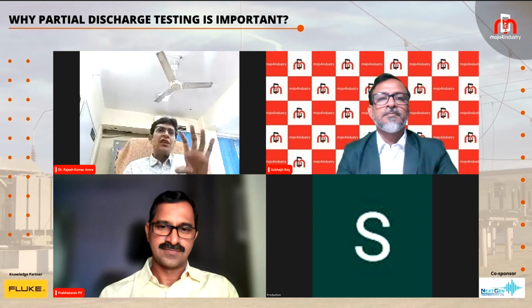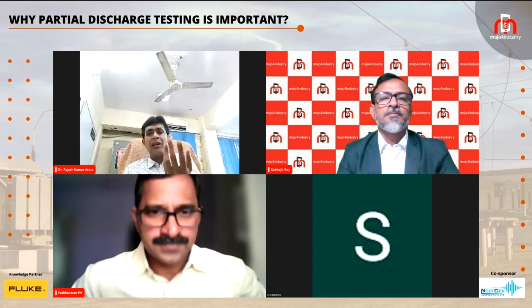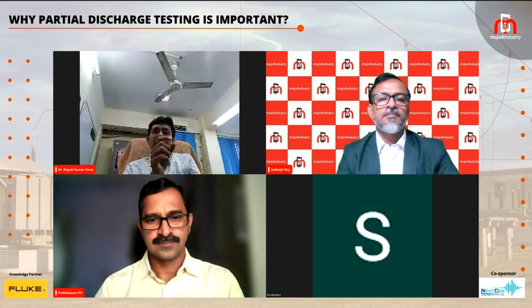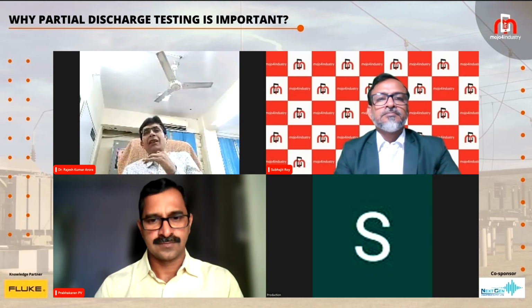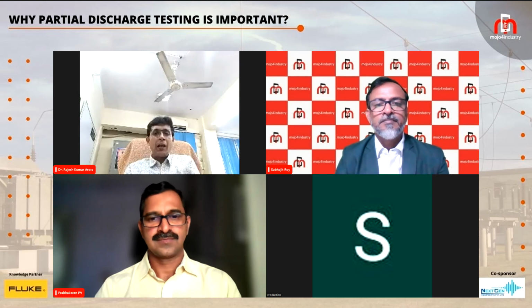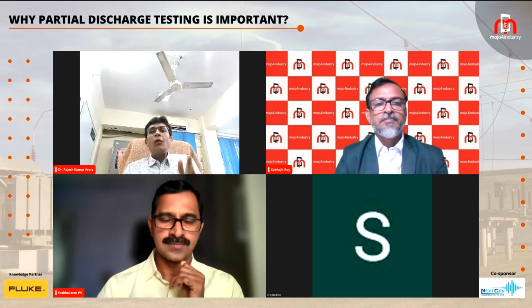Now the topic is partial discharge. In very simple words, to help you understand what partial discharge is: basically, it is leakage in the dielectric system that doesn't make a complete bridge between the live part and the ground, or between 2 live parts in a 3-phase system. It is a kind of bridge that is not permanent, that may be intermittent, that is partial in fact, and the name implies it is a partial discharge. Whenever it happens, it brings an inhomogeneous electric field. When an inhomogeneous electric field is there in any equipment, one thing is bound to happen, that is breakdown. And we have to avoid that breakdown by proper measurement of partial discharge as the end user.